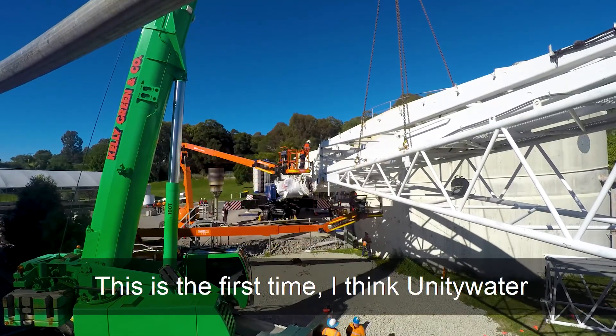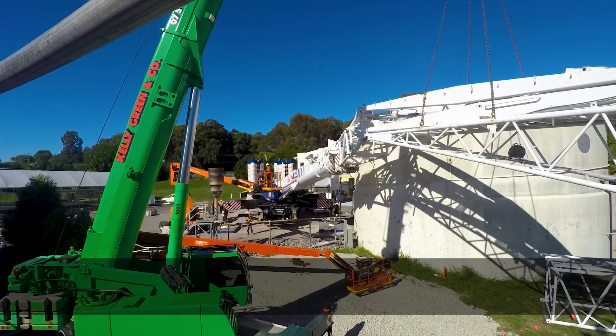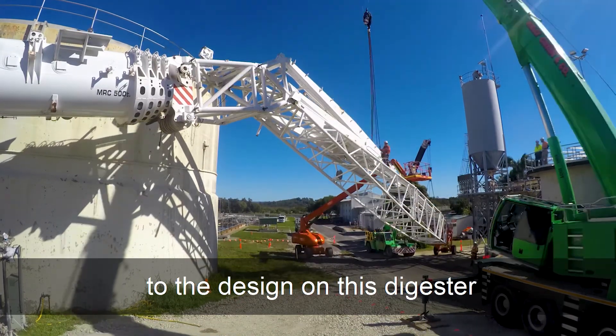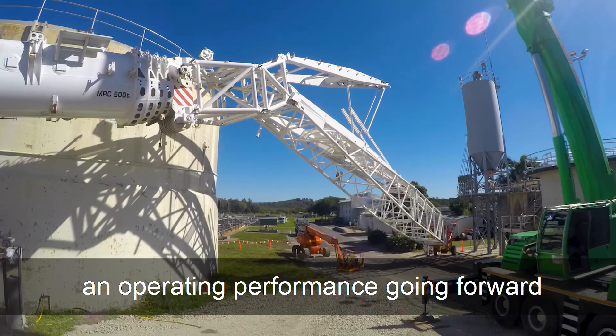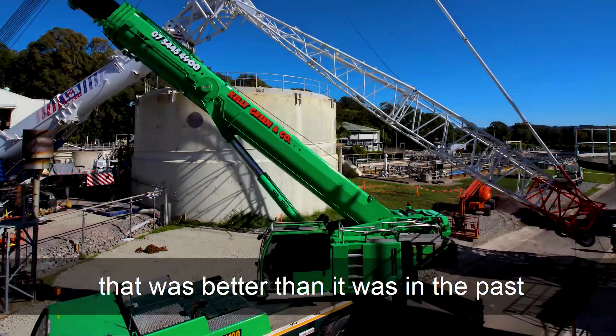This is the first time I think Unitywater has actually taken a digester offline full-scale like this and lifted the roof off. The key thing now is to identify the root cause of failure so we can make amendments to the design on this digester, to ensure that it's going to have an operating performance going forward that was better than it was in the past.